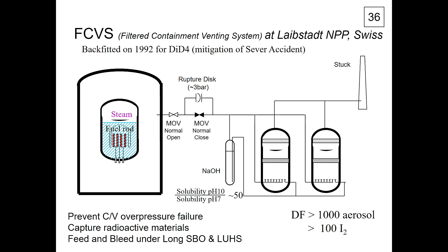Looking at the filtered venting system at Leibstadt nuclear power station, this is a Swiss BWR system. The Swiss government ordered mitigation of severe accidents and backfitted this filtered venting system in 1992. In case of high pressure in the containment vessel, it automatically releases steam to the atmosphere, and it has a filter so cesium and strontium may be captured, allowing filtered steam to be released to the atmosphere. This system has been implemented since 1992, more than 30 years ago.